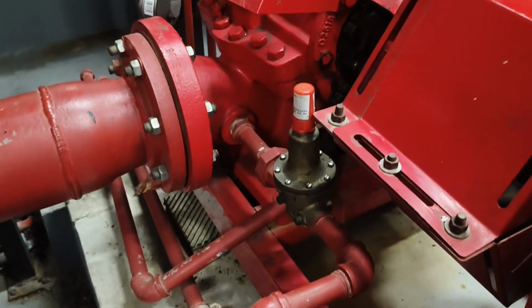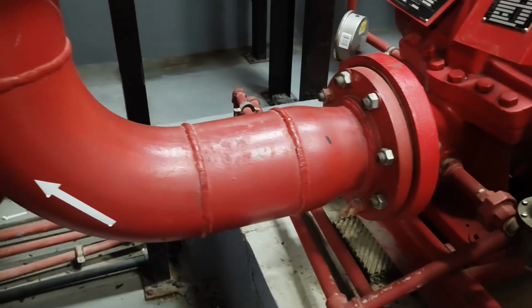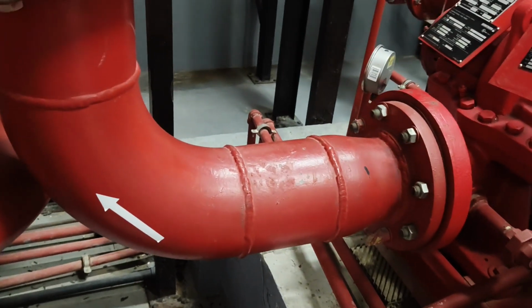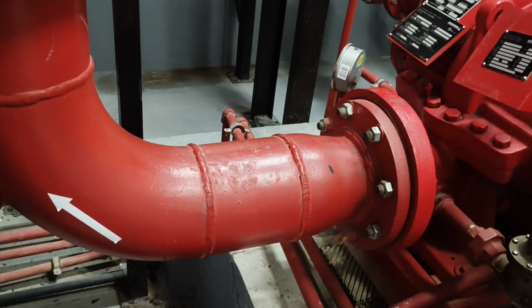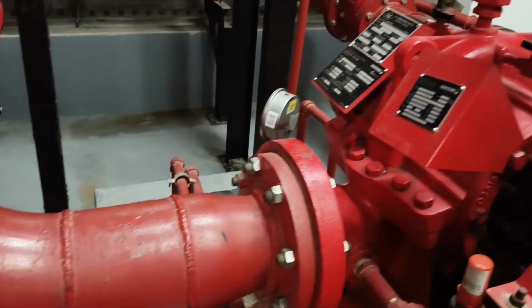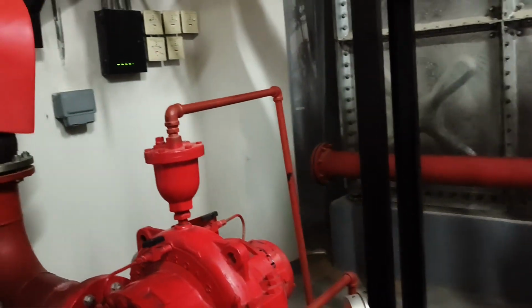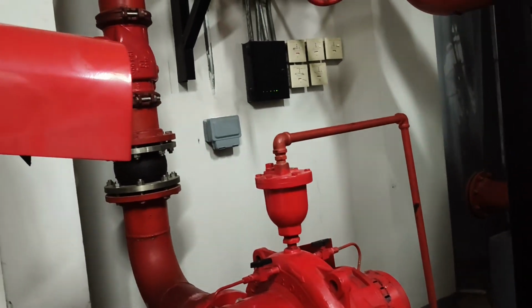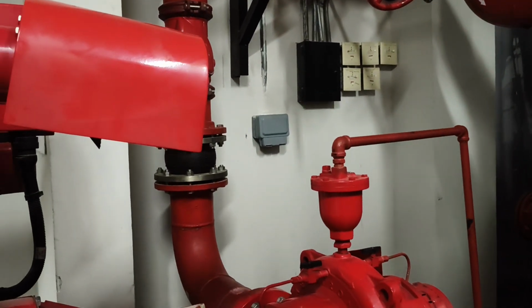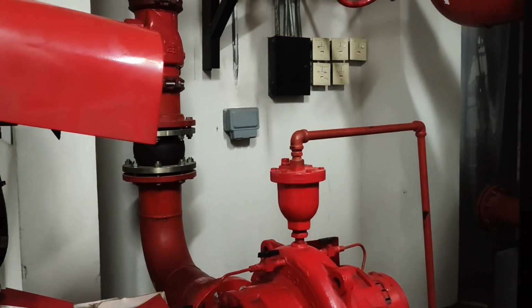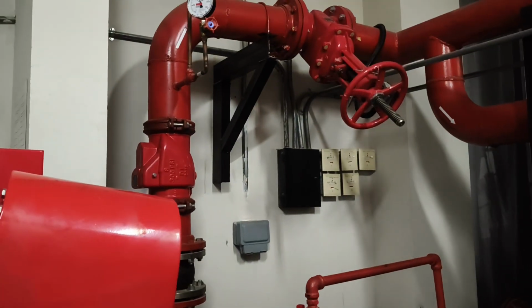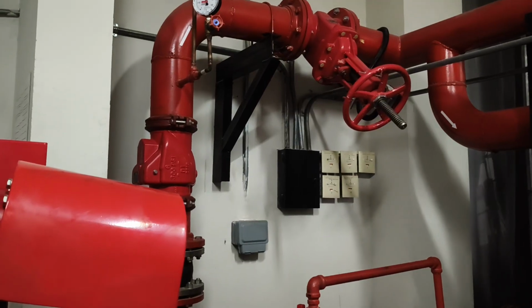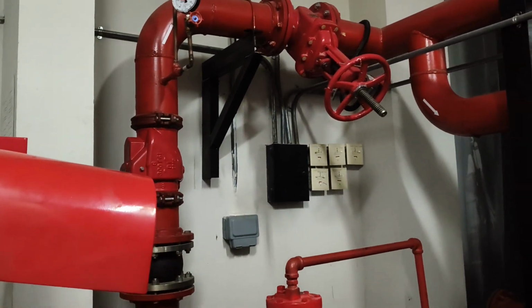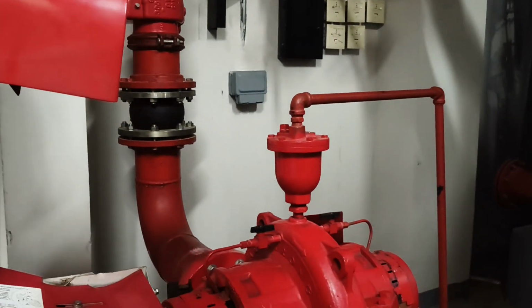It's mainly found on the electric. The diesel, most especially diesel, is supposed to have what we call the release valve, the pressure release valve. But this system, the pressure is good, so I think they did not add that. It's supposed to be before the check valve, but you can see it's not there.